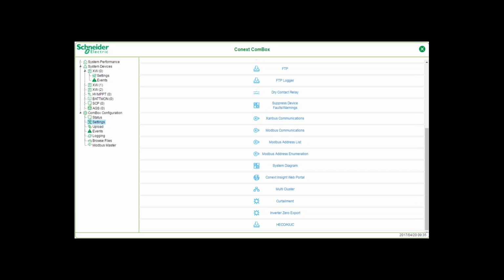Curtailment, which is related to AC coupling. It's actually a frequency shift, so in a backup scenario, the XW shifts the frequency once float voltage is reached to protect the battery. So the grid tie inverter is going to respond one of two ways. Depending on whether it has curtailment capability, it'll either throttle down the output or it'll shut off and count down for 5 minutes and come back online.